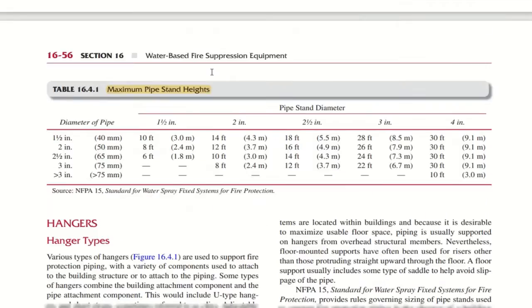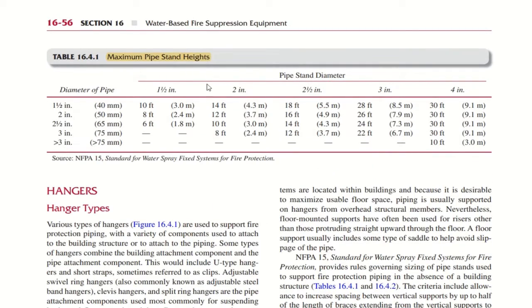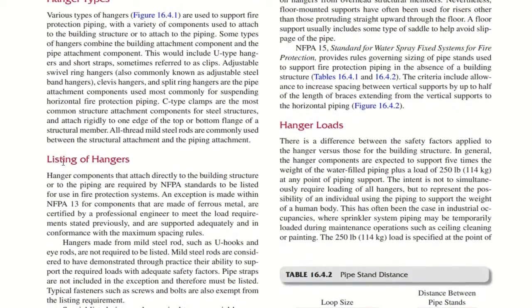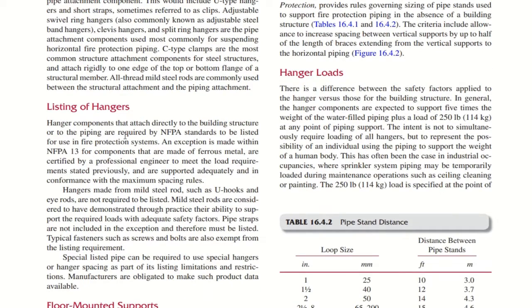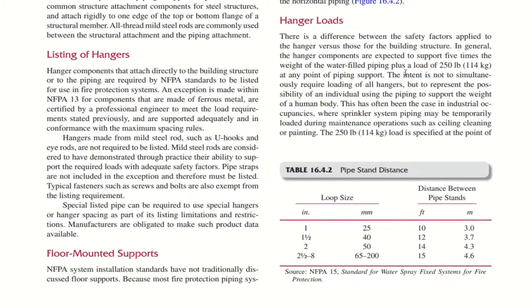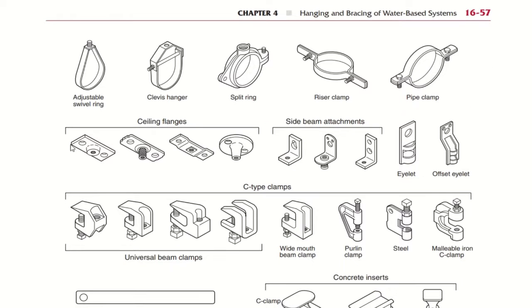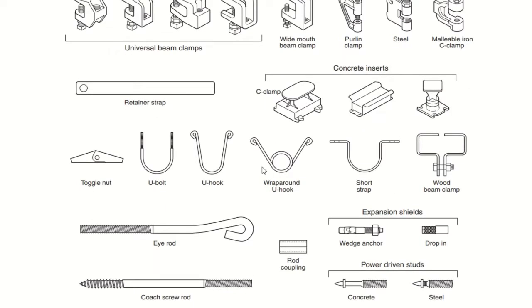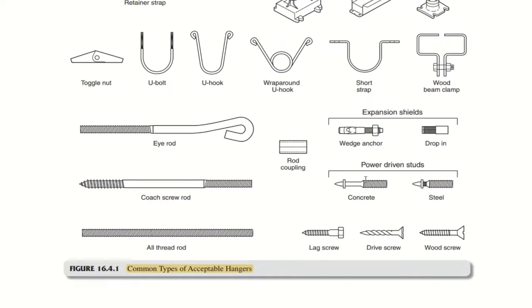So here in chapter 4 we are going through the hangers and supports. Basically the maximum pipe stand heights, they have just given the pipe stand diameter and the diameter of the pipe. Just go through this table, and the hangers must be listed as per NFPA 13. Hanger loads they have given, so this is an important point you need to remember: hanger load, how much it has to support. There are various types of hangers like swivel hanger, clevis hanger, split rings, riser clamps, pipe clamps, and so on. So just go through these U bolts and U hooks and so on.